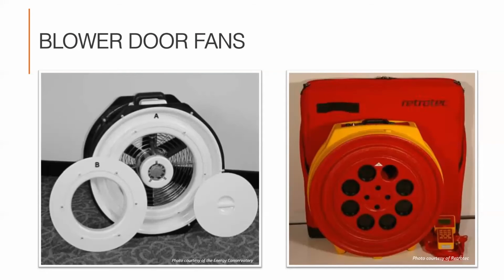I want you to notice the white plastic rings on the face of the Minneapolis on the left. It has the A ring on it, which is common for testing average size homes. You can remove that A ring and test with the face of the fan wide open. That's common for bigger and leakier homes. And you can also add the B ring to accurately measure smaller and tighter homes. You, the auditor, get the opportunity and responsibility to do what's best for that particular house.